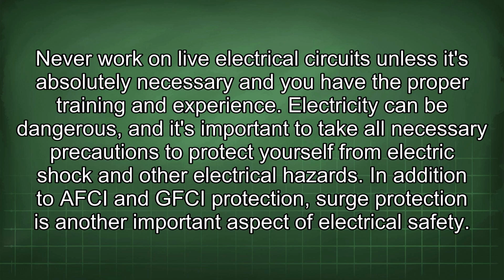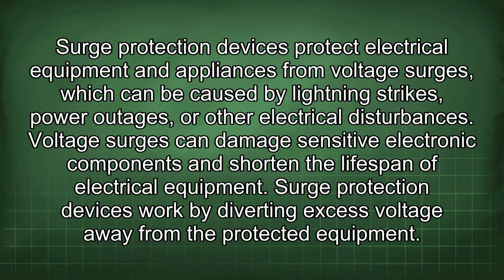electrical hazards. In addition to AFCI and GFCI protection, surge protection is another important aspect of electrical safety. Surge protection devices protect electrical equipment and appliances from voltage surges, which can be caused by lightning strikes, power outages, or other electrical disturbances. Voltage surges can damage sensitive electronic components and shorten the lifespan of electrical equipment. Surge protection devices work by diverting excess voltage away from the protected equipment.